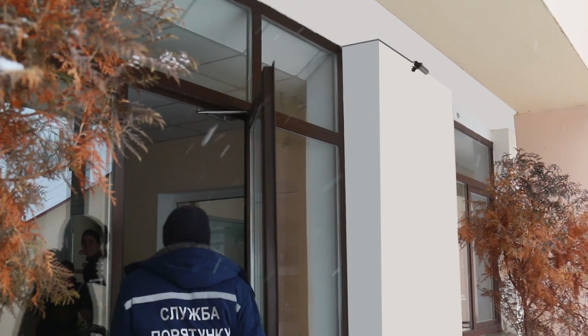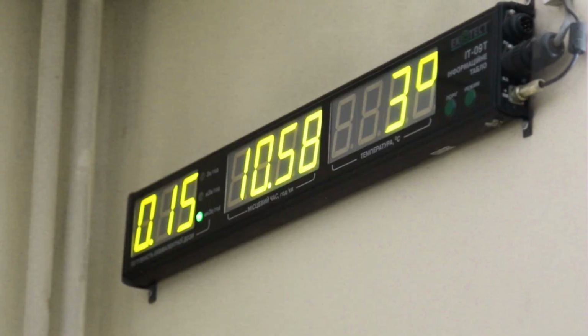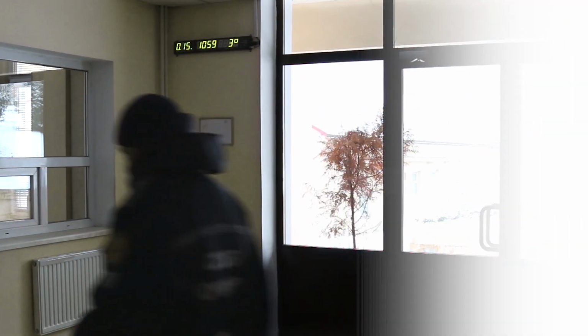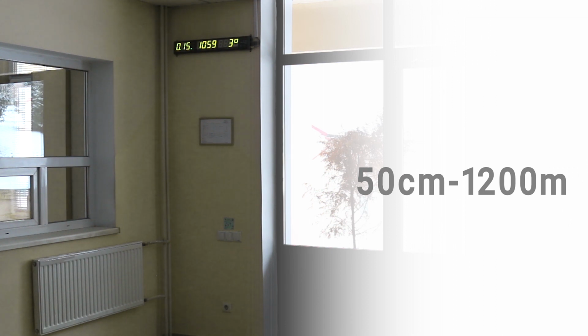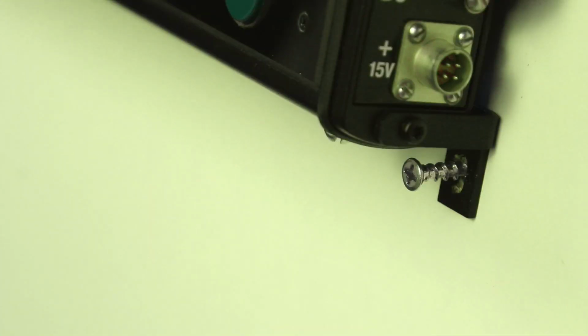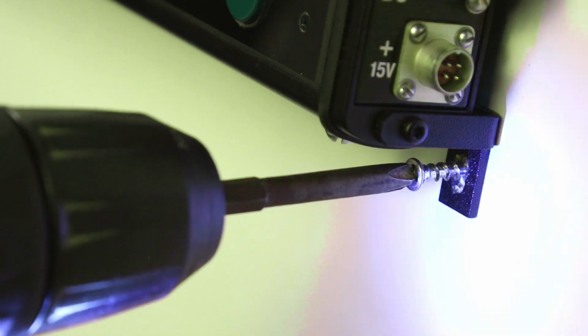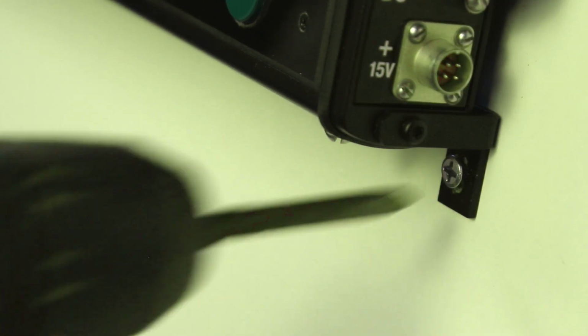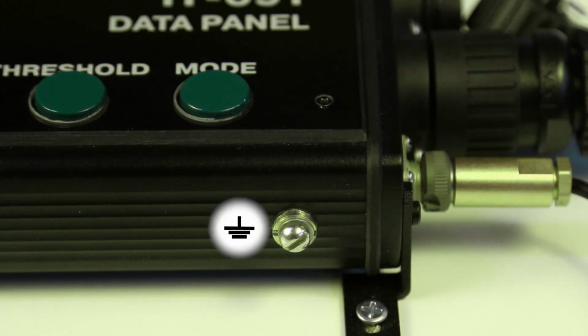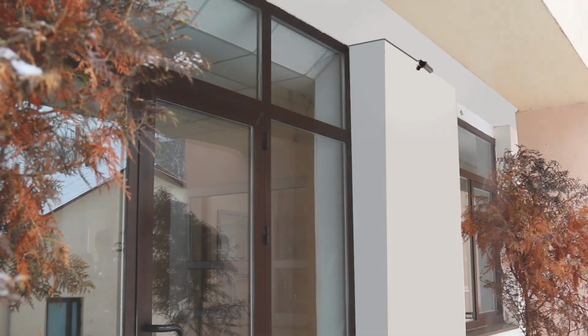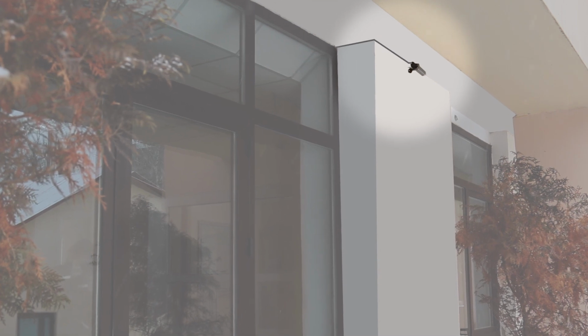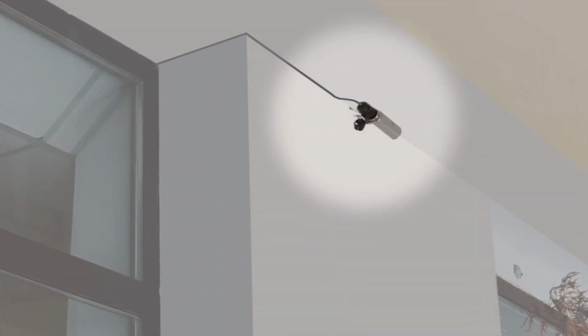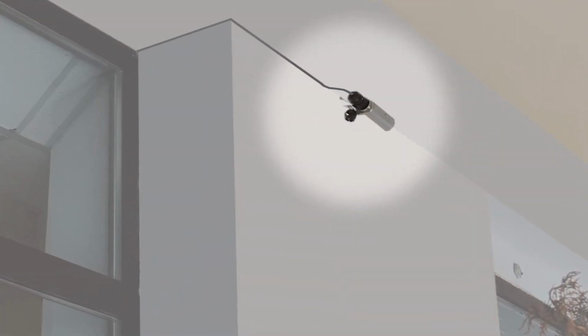The detection unit should be placed outside of the facility and the data panel inside. The distance between them is from 50 centimeters to 1,200 meters. For installation of both devices, fasteners are included in the delivery kit. The panel should be grounded. Choose a spot where direct sunlight does not reach the detecting unit, as heating of its case will cause incorrect measurements of the temperature.